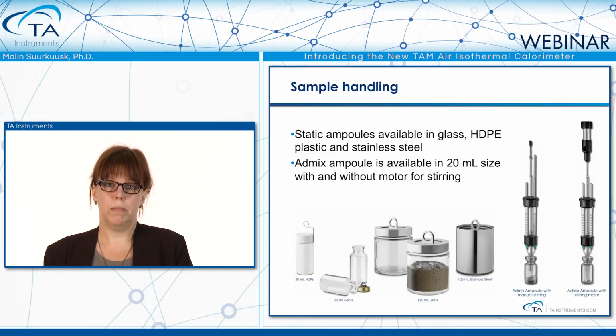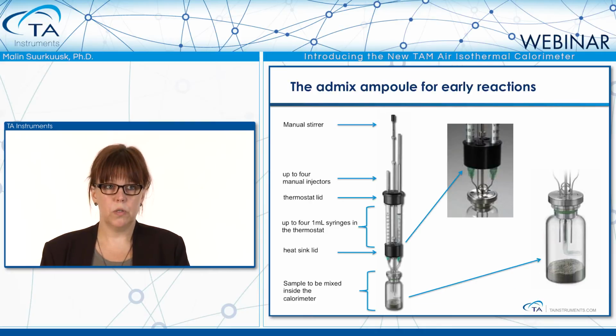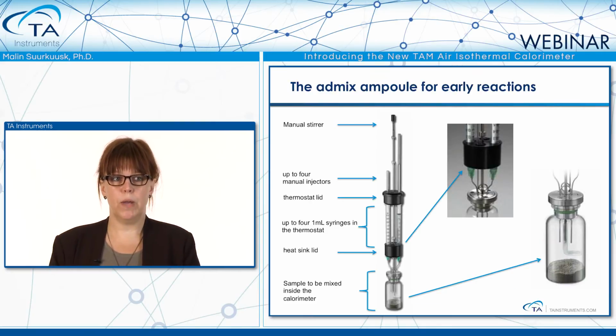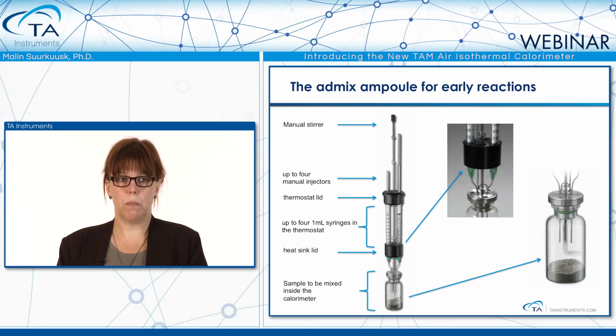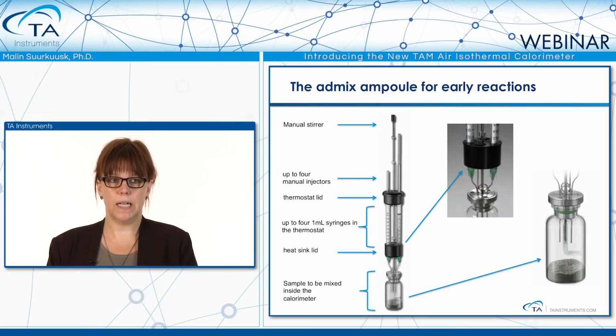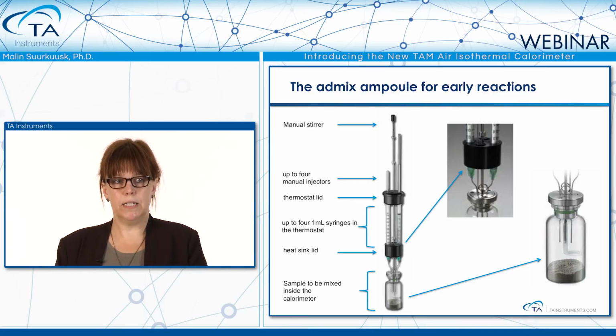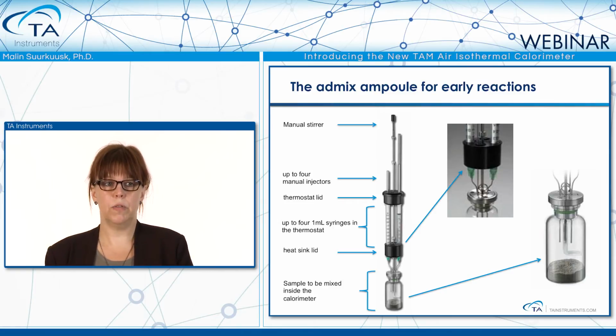For the 20 milliliter calorimeter, the 8-channel standard volume calorimeter, we also have what we call the admix ampule, as I mentioned, and that makes it possible to add and mix samples inside the calorimeter. It can come with manual stirring or with a motor stirrer to be able to stir the sample inside. If we have a closer look at the admix ampule, which is used for early reactions, in the bottom you put your sample to be mixed, and this part with the glass ampule in the bottom, that's what sits inside the calorimeter. Above we have a heat sink lid, and that's the lid that sits in the secondary heat sink of the calorimeter.